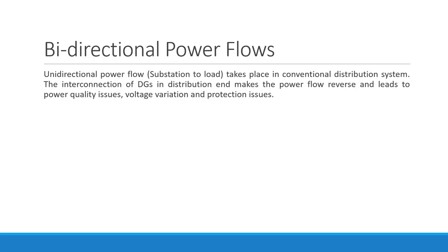Bidirectional power flow. Already we said reverse power flow is possible. Unidirectional power flow takes place in a conventional distribution system. The interconnection of DGs in distribution makes the power flow reverse. We said that surplus power can be sold. It means power flow will be from the microgrid to the main grid, that is the reverse flow of power, and it leads to power quality issues. So what would happen when there is bidirectional power flow? There may be issues with power quality, issues with voltage variation as well as protection issues. Accordingly, you need to set the relays, or the protection scheme should be designed.